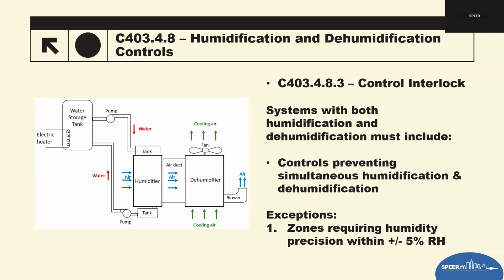Zones requiring very precise humidity, we've already talked about that, within plus or minus 5% relative humidity may use this simultaneous operation, but this must be specifically justified by code, accreditation, or approved by the authority having jurisdiction. So code officials can make that call. Why this matters is humidity control is one of the biggest contributors to HVAC use in commercial buildings.